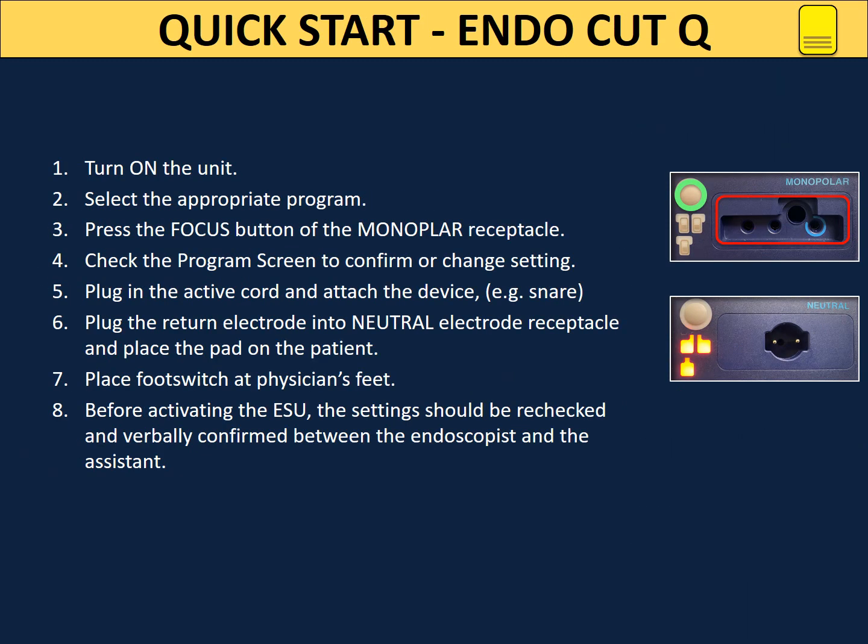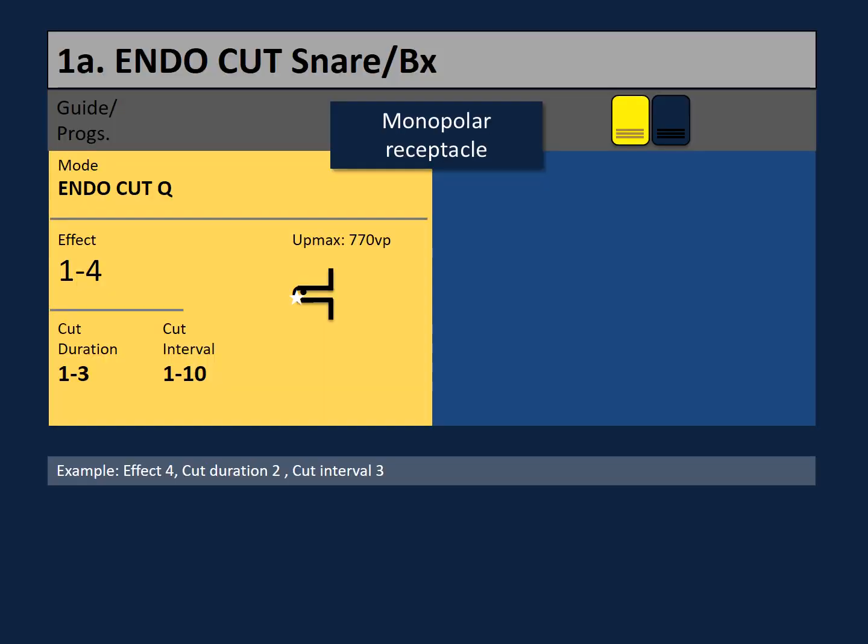For a quick start using the EndoCut Q: always position the machine where you can see it. Turn on the unit. Select the appropriate program. Press the focus button of the monopolar receptacle. Check the program screen to confirm or change settings. Plug in the active cord and attach the device. Place the pad on the patient and plug the return electrode into the neutral electrode receptacle. Position the footswitch well. Before activating the ESU, the settings should be rechecked and verbally confirmed between the endoscopist and the assistant. It is recommended to always start by using the lowest possible setting that will achieve the desired surgical effect.